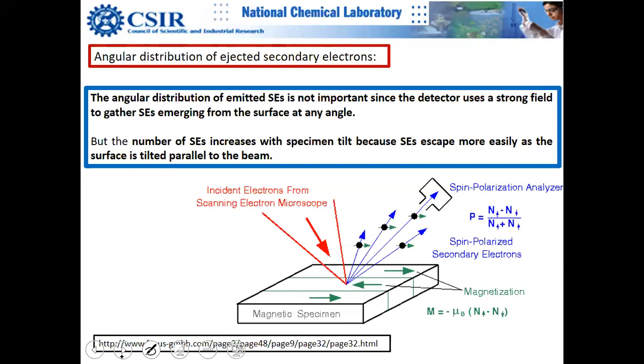For physics students interested in magnetism: if you have a magnetic sample with magnetic domains, electrons emitted from these domains will be spin-polarized — their spins polarized by the direction of the magnetic field. If your analyzer can detect electron spins of different directions, you can image the magnetic domains in SEM.